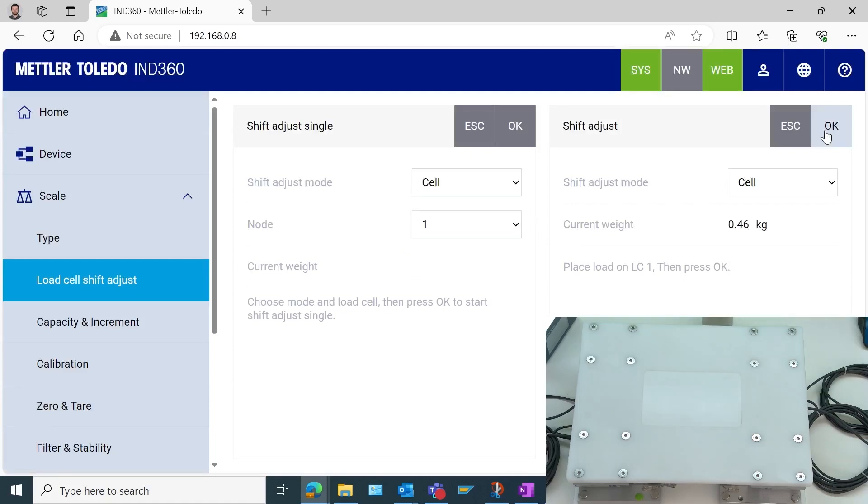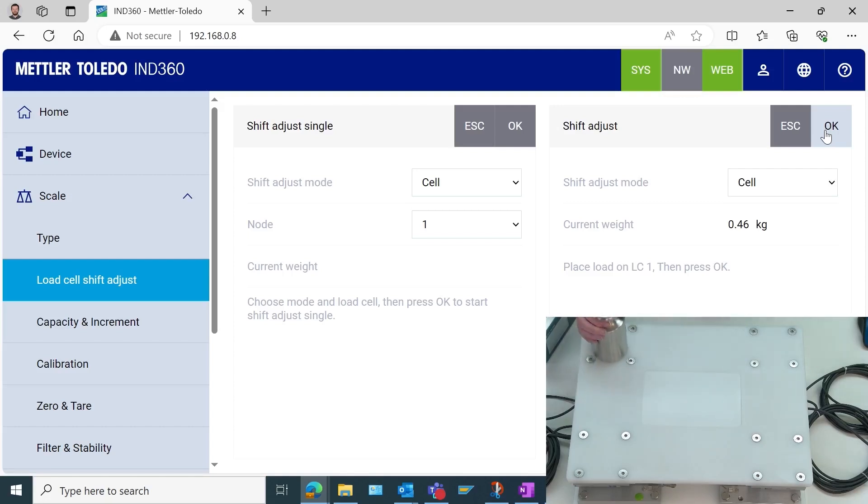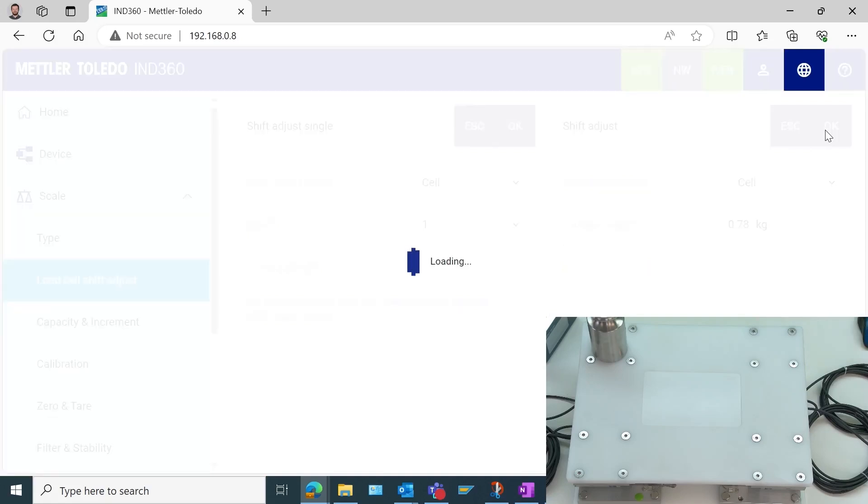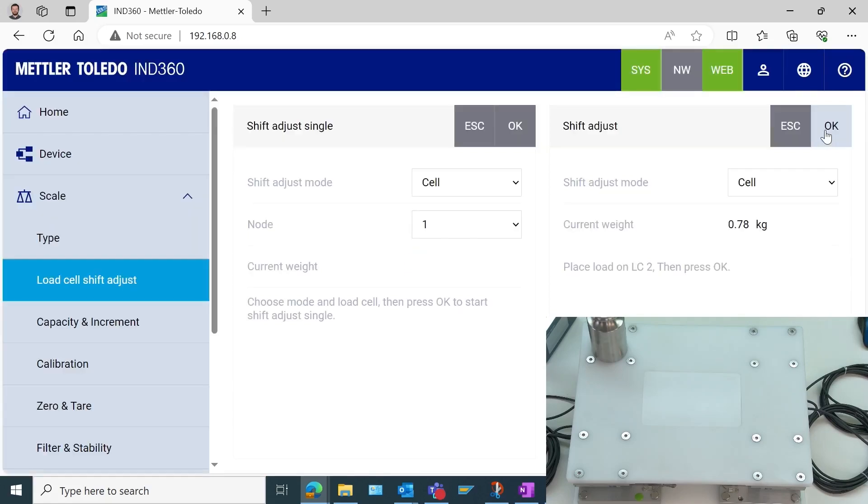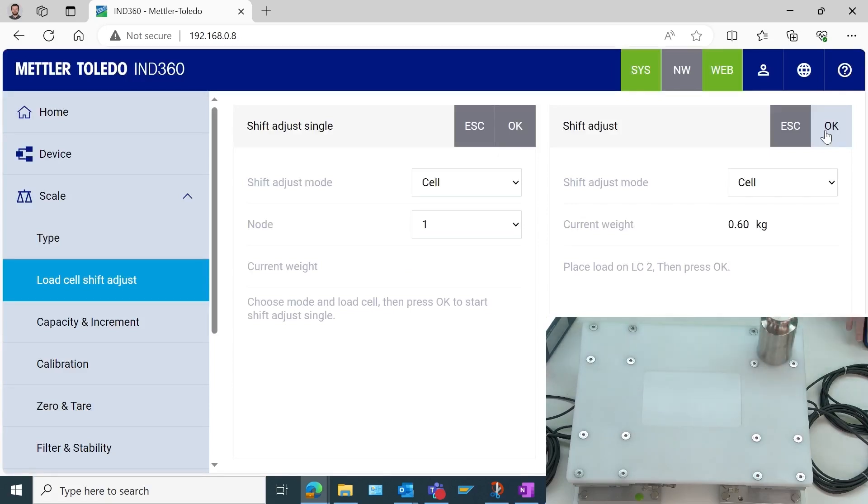Now it's telling me to place it on load cell number 1. This is where we want to be careful. The multi-ACM junction box has specific labels for load cells 1, 2, 3, and 4. You can also see that on the outside of that junction box. We just want to make sure that when we're placing this test weight, we know where load cell number 1 is. I happen to know that it is right here, so I've placed that, and I will select OK.